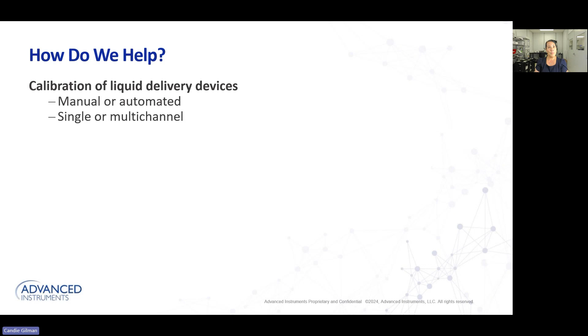There also comes a time where interim volume verification has to happen. So you've got your calibration schedule that maybe happens every 6 months or once a year, but maybe there's a need to perform interim volume verification on those devices. And those interim volume verifications could occur on liquid handler devices as well as pipettes in between those calibration cycles. Assay development. So oftentimes assay development happens on the bench where there's a lot of manual pipetting technique involved. And then that gets transferred over to the automated side of the house. And so what happens when those two sides don't have answers that match? And you have an assay that has two different results based on whether it's on the bench or on automation. We can help with that.